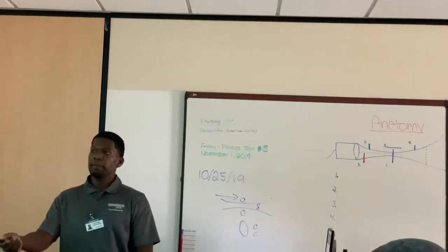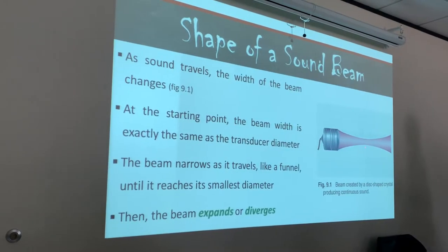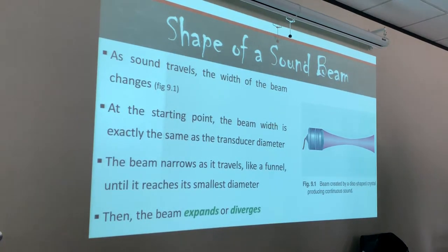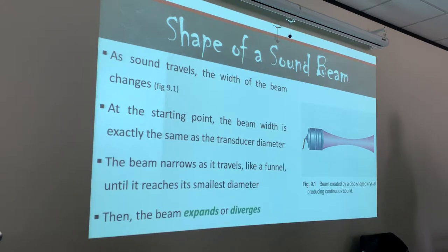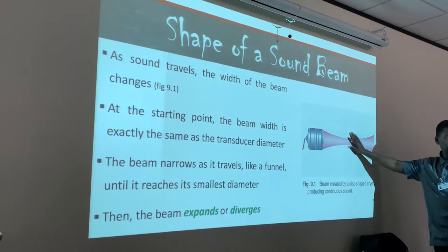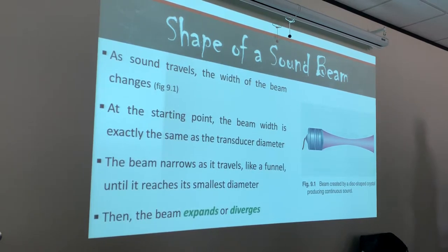At the starting point, the beam width is exactly the same as the transducer diameter — immediately exiting that transducer. The beam narrows like a funnel until it reaches the smaller diameter — that's going to be our focus right there. When you're moving your focus up and down, we're actually changing the shape of the beam. Our best images are going to be in this space before the beam starts to diverge. That's why I always want you to put your focus on the posterior border of the anatomy — I want all of my imaging to come from the near field, not the far field, as the beam is converging, not diverging.